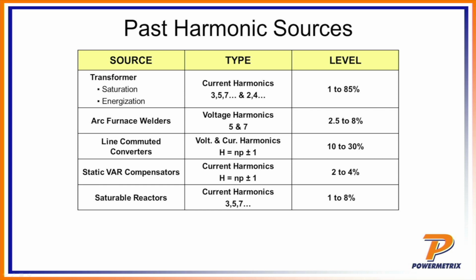Mentioned arc furnaces, arc welders, things that are drawing large transients of current will generate a large amount of harmonic energy. It can generate voltage harmonics on the 5th and 7th anywhere from 2.5 to 8%. Some other examples are line commutated converters, static VAR compensators, saturable reactors. Once again, that's older equipment that can cause a variety of different harmonics, anywhere from a few percent to several tens of percent.